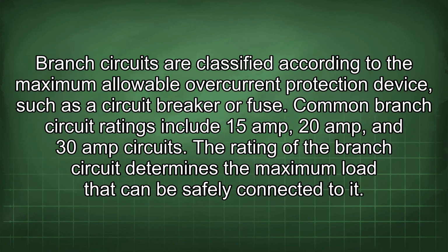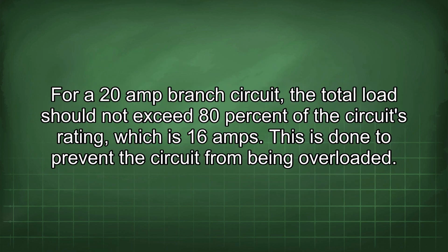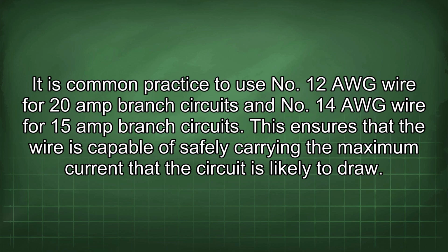Branch circuits are classified according to the maximum allowable rating of the overcurrent protection device, such as a circuit breaker or fuse. Common branch circuit ratings include 15 amp, 20 amp, and 30 amp circuits. The rating of the branch circuit determines the maximum load that can be safely connected to it. For a 20 amp branch circuit, the total load should not exceed 80% of the circuit's rating, which is 16 amps. This is done to prevent the circuit from being overloaded. It is common practice to use No. 12 AWG wire for 20 amp branch circuits and No. 14 AWG wire for 15 amp branch circuits. This ensures that the wire is capable of safely carrying the maximum current that the circuit is likely to draw.